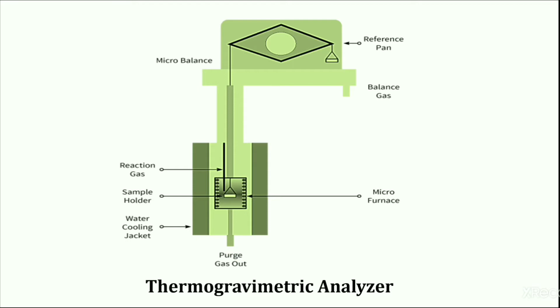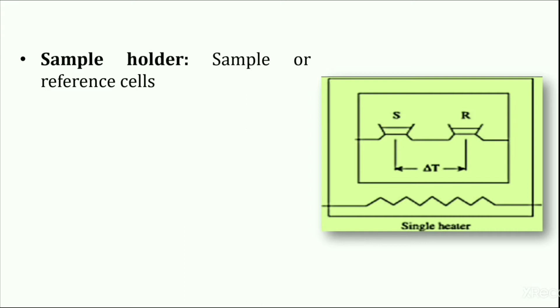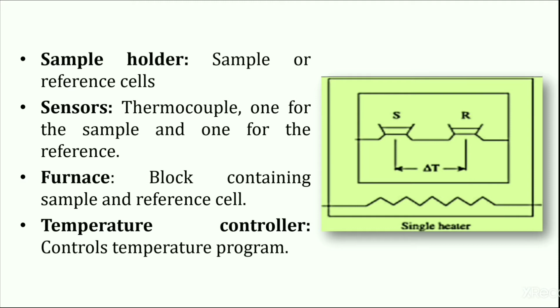The sample holder is used to hold the sample or reference compounds. Modern instruments contain auto samplers, which help to load the samples on the microbalance. Thermocouples are used in the instrument as sensors. One thermocouple is used for the sample and the other one for the reference. The furnace is made of quartz and can raise the temperature as high as 1000 degrees Celsius. Care should be taken at all times that the thermocouple is not in touch with the sample, which is in a platinum pan. In the instrument, temperature is regulated through a temperature controller.